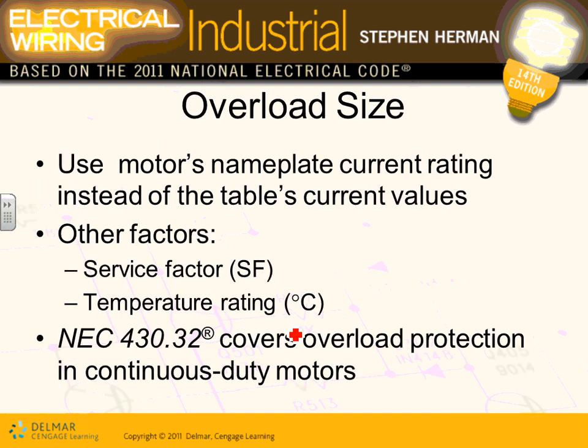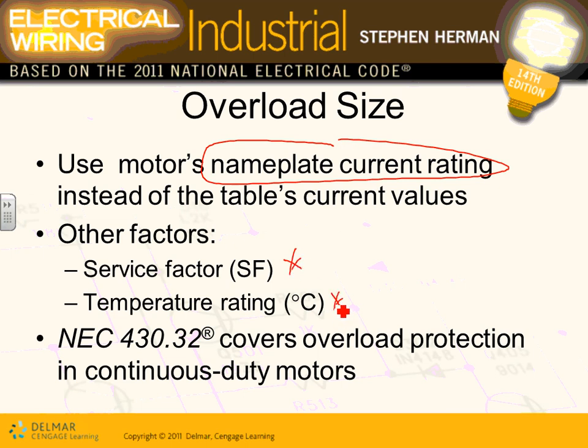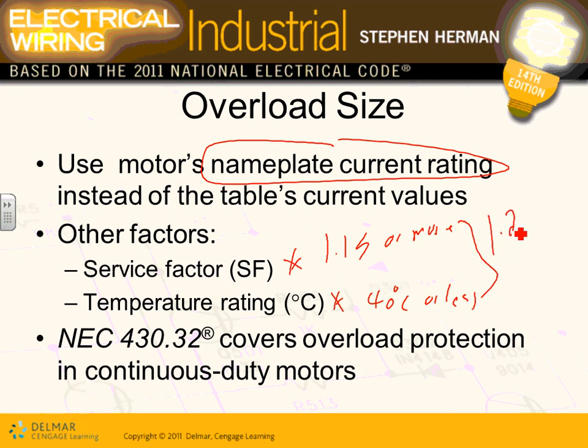When sizing the overload, you use the nameplate full load current — very important. Two factors apply: if the service factor is 1.15 or more, or temperature rise is 40°C or less, use a 1.25 multiplier. For all other cases, use 1.15. This information comes directly from NEC 430.32, and you will be tested on it next week.